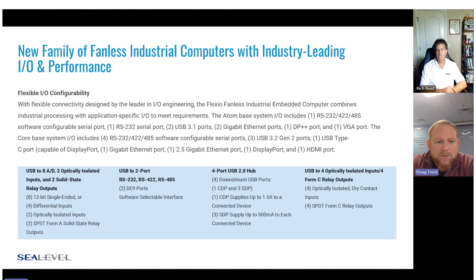I'd like to take a minute and go through some of those options. The base model has what I've already mentioned, but some customers might want more analog and digital IO. We have one option that incorporates eight 12-bit analog inputs, four differential inputs, two isolated inputs, as well as two solid-state relays — that's an expansion above the standard IO. Other applications might require additional serial ports, so we can add two additional serial ports right into the system as a build option.